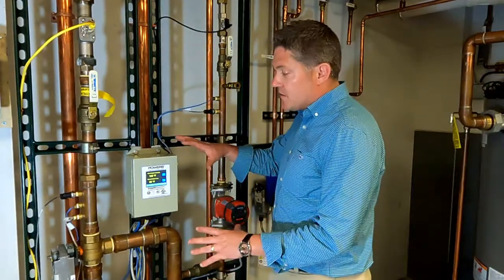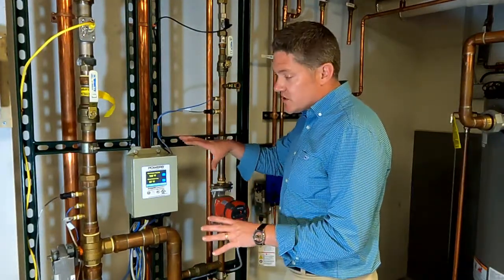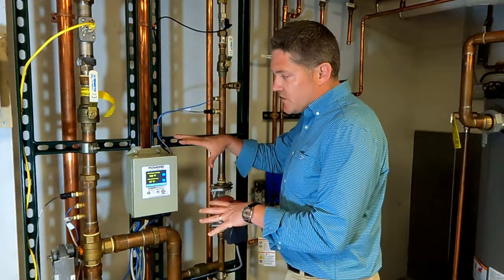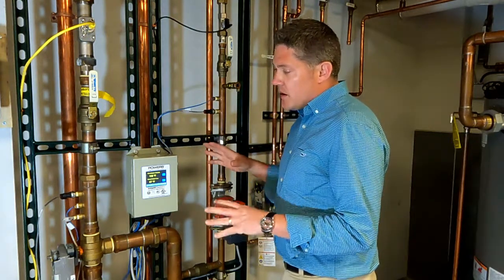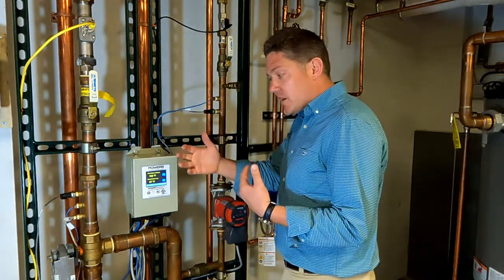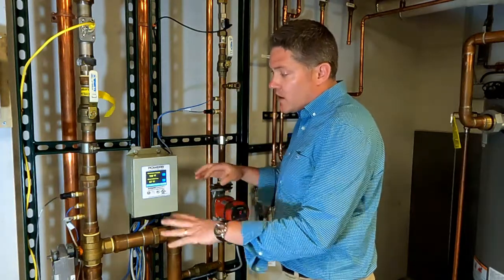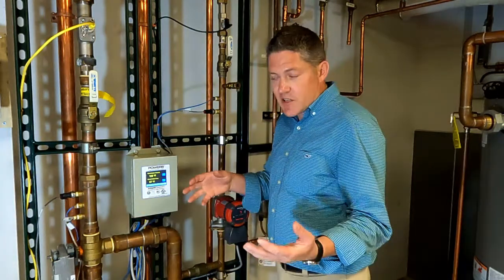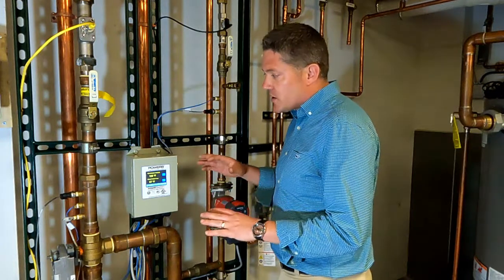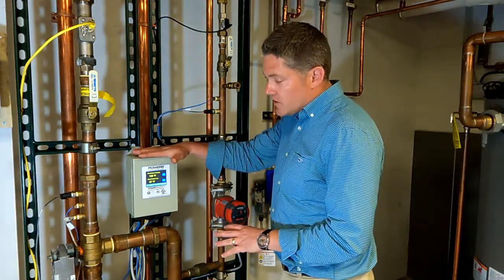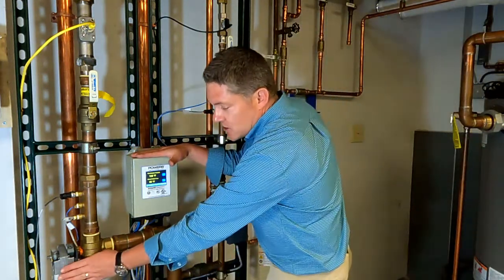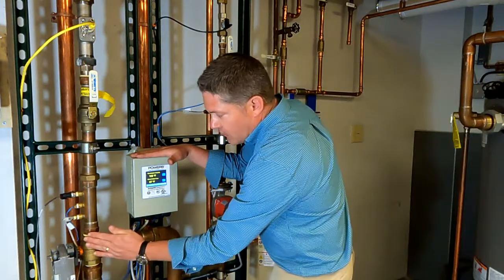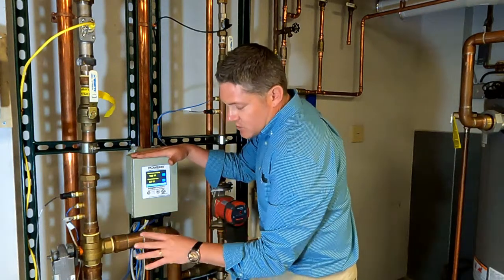Okay, so here we have the Powers Intellistation Sr. This is the first digital mixing valve that Powers put out. It has the plus or minus from set point rating of 2 degrees versus the thermostatic, which is going to be plus or minus 7 degrees. So a little bit tighter control on the temperature. It has the actuator, a 3-port ball valve, and then a variety of sensors that we'll talk about.